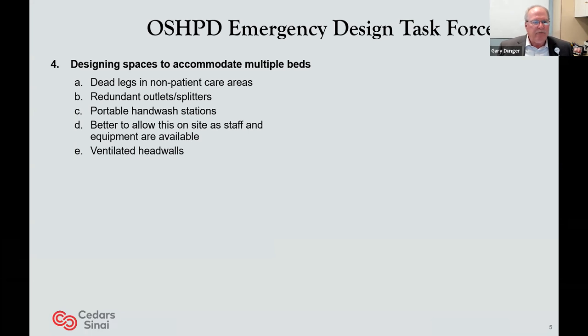Taking into account the need for redundant outlets in areas where you probably wouldn't anticipate needing them, having splitters available for medical gas outlets. How about providing portable hand wash facilities, because the patient rooms require a hand wash lavatory in the room, having portable hand wash facilities available for when you need them is something to consider.